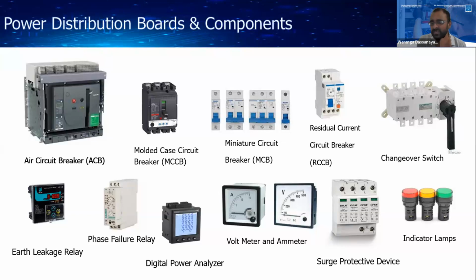Then digital power analyzers are used to analyze the power available in the system. You can read the voltage and the current level, and some analyzers can also measure the harmonic levels. The digital power analyzer can be used to take system parameters like voltage and current. Next, you can see some voltmeters and ammeters also. Then surge protective devices, which are used to protect the system from lightning or switching transients. So this is also a very important device in a low voltage system. Then the indicator lamp, which indicates the availability of power. So basically, you have to know these major components in the electrical panel to examine the power distribution system.